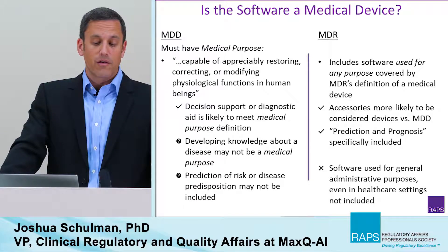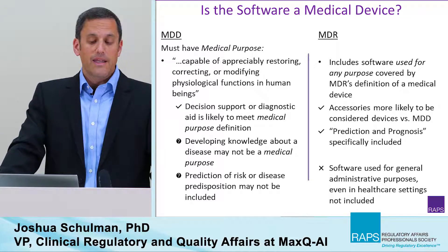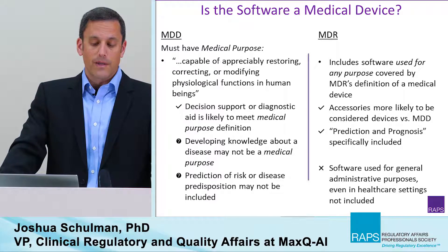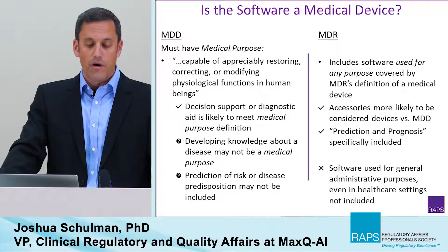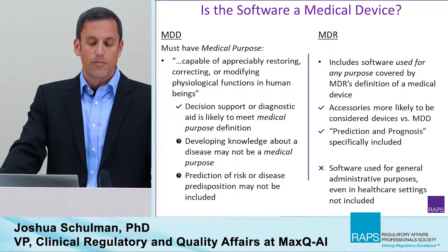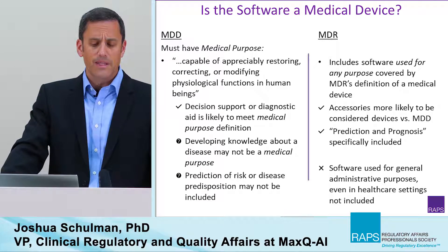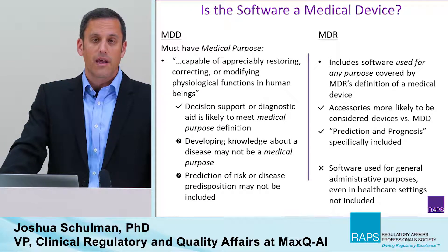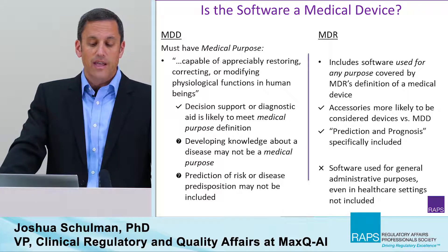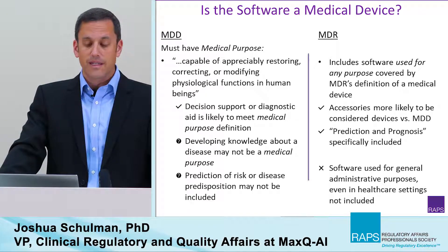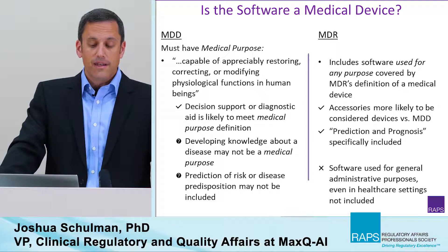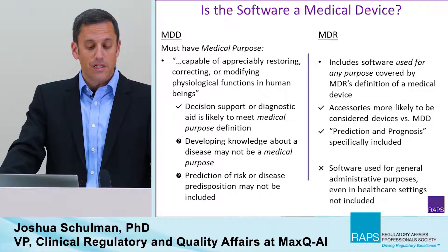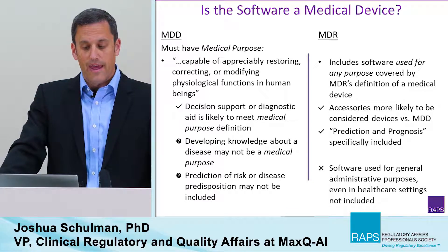Under the existing Medical Device Directive, it needs to have what's known as a medical purpose — a device capable of appreciably restoring, correcting, or modifying physiological function in human beings. When it comes to things like decision support or diagnostic aids, those are likely to meet the medical purpose definition. However, devices that are designed to develop knowledge about a disease or predict risk or disease predisposition may or may not fall under that category.